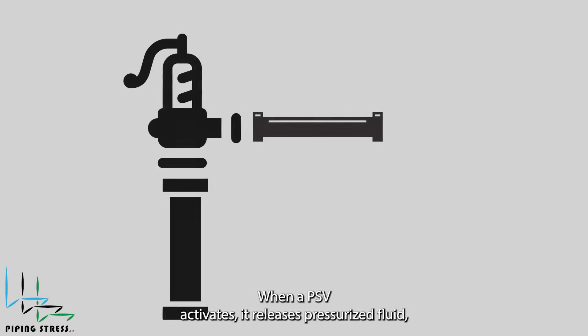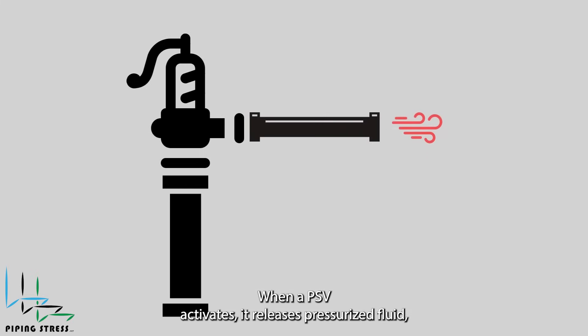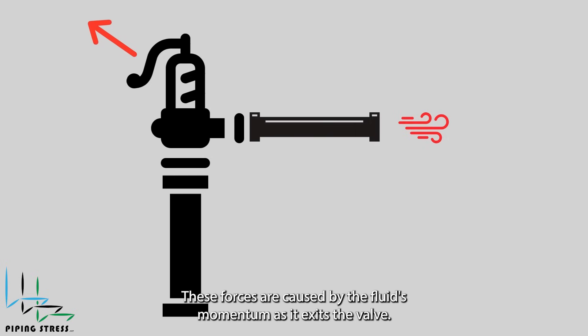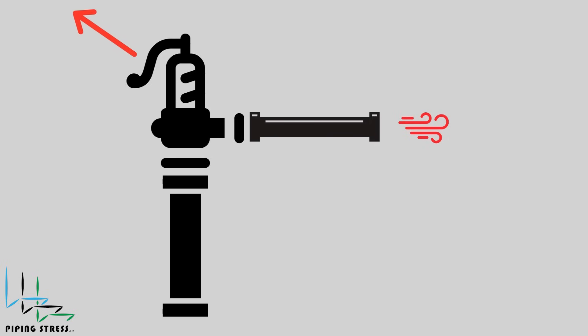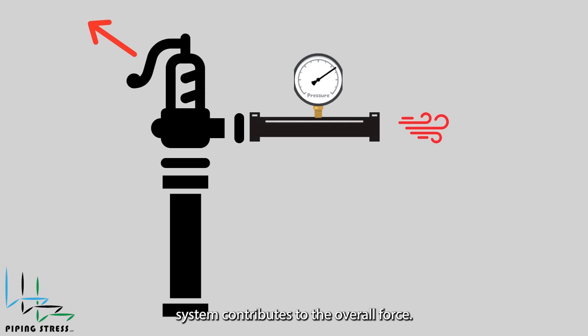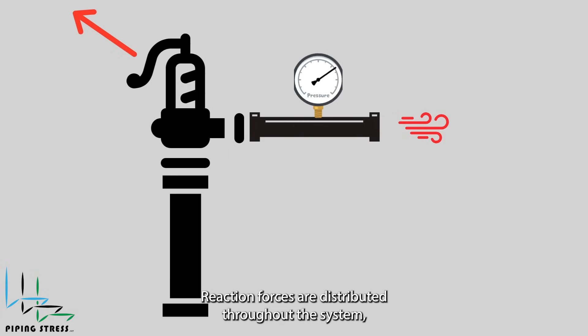When a PSV activates, it releases pressurized fluid, creating reaction forces. These forces are caused by the fluid's momentum as it exits the valve. Additionally, back pressure within the discharge system contributes to the overall force. Reaction forces are distributed throughout the system, but special attention is needed at the valve outlet.